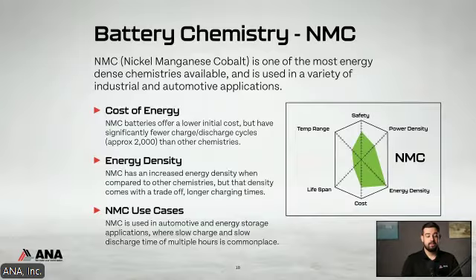So NMC. NMC is one of the most energy dense chemistries available right now. It is not that expensive, but there are trade-offs, right? So it's very energy dense and it can deliver a lot of power quickly, but the cycle life of an NMC battery is very low. So typically 1,000 to 3,000 cycles, depending on your ambient environment and depending on your C rates that you charge and discharge at. It is not as safe as other chemistries. Thermal runaway can be induced very easily with NMC.